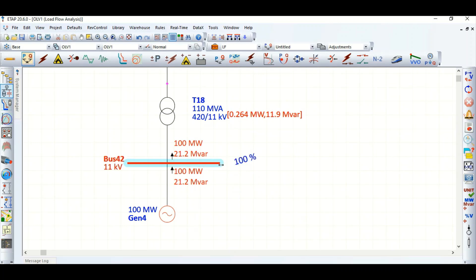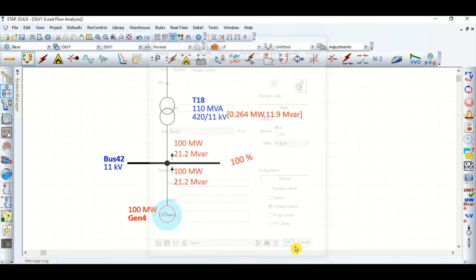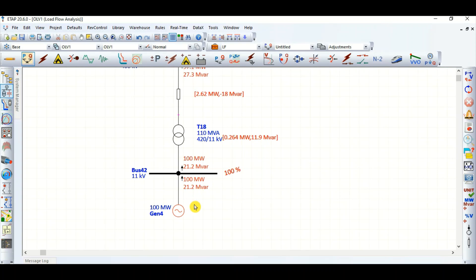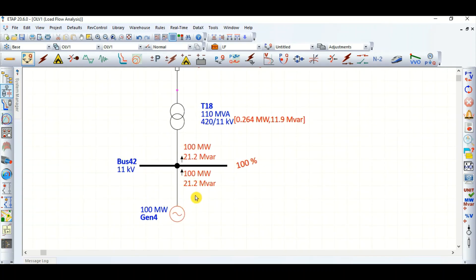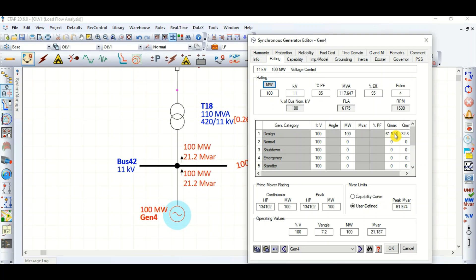The generator bus voltage is maintained at 100% because the generator is operating in voltage control mode — meaning the exciter or AVR is set at voltage control mode. The generator voltage is maintained at 100%, and now it is supplying 21.2 MVAR. The generator is capable of supplying up to 61.974 MVAR.